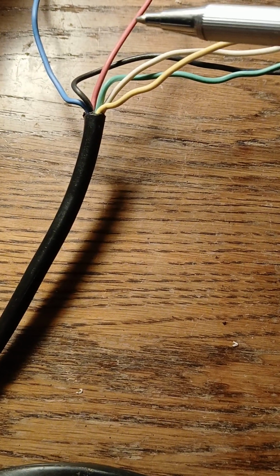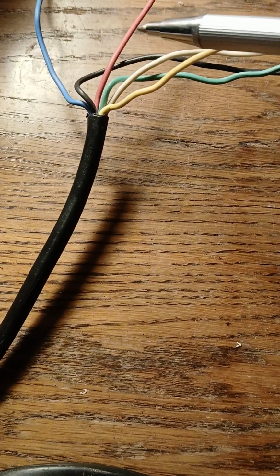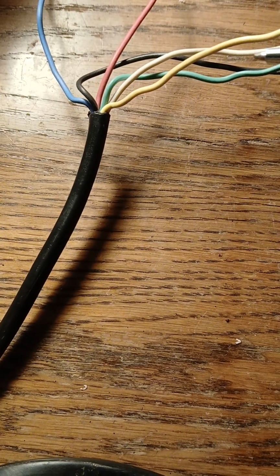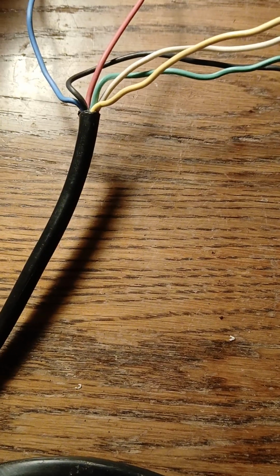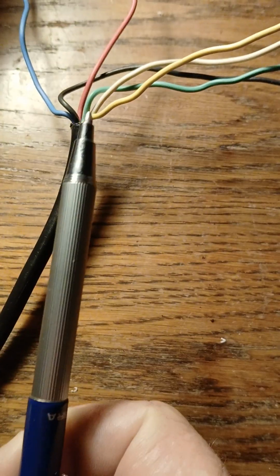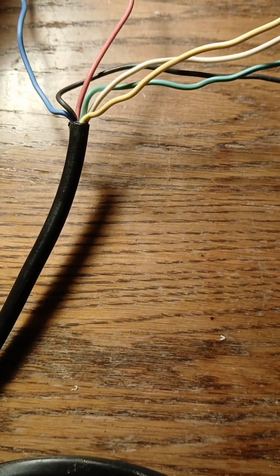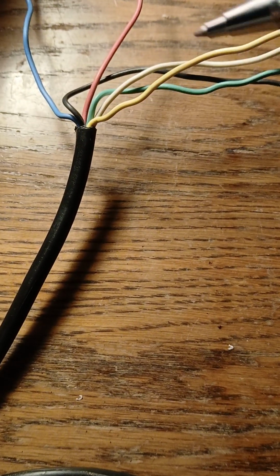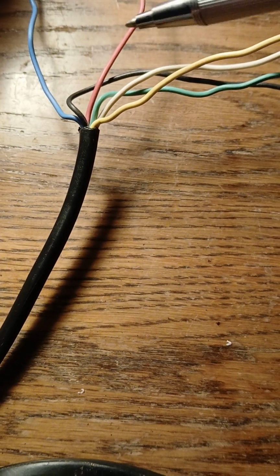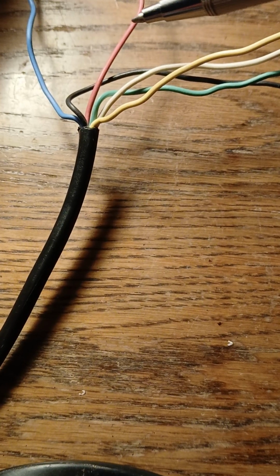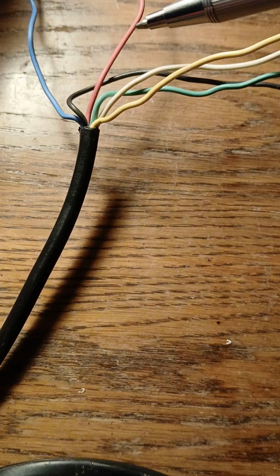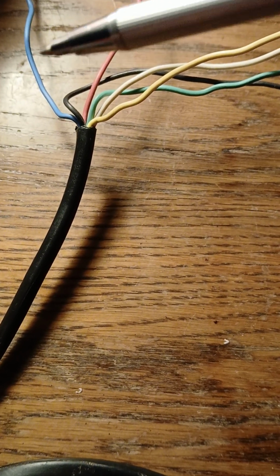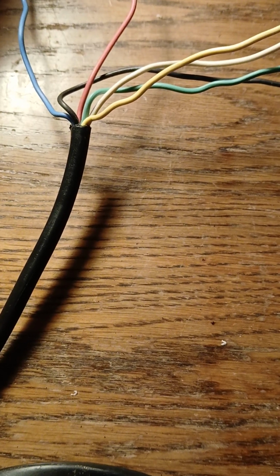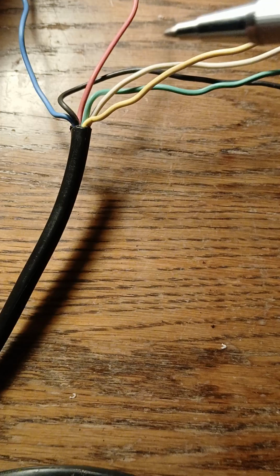But hypothetically, if we're in heat mode, we go here and we jump her over here. So now the red wire's hot and the white wire's hot and the green wire's hot. It goes back to the computer board through the air handler, and the sequence of operation happens. But keep in mind, when we're powering this 24 volts, it should come up this way to the thermostat, go through the common. The common should be commonly connected. So these are the two important wires that are your low voltage. Your 24 volts is your red, your power wire, and your blue is, generally speaking, your common wire. Not always, it's not universal, but it's pretty standard in the industry.